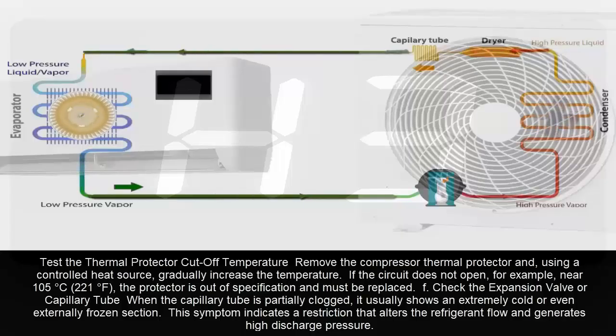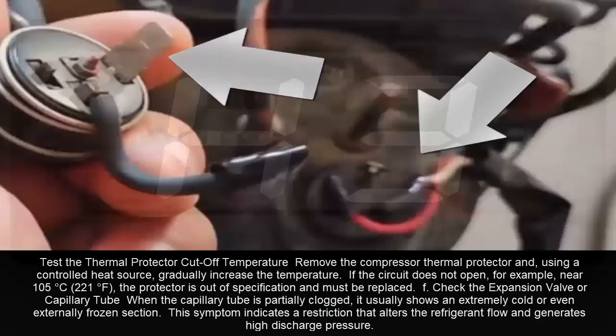Test the thermal protector cutoff temperature. Remove the compressor thermal protector and, using a controlled heat source, gradually increase the temperature. If the circuit does not open, for example near 105 degrees Celsius, the protector is out of specification and must be replaced before installing the compressor.